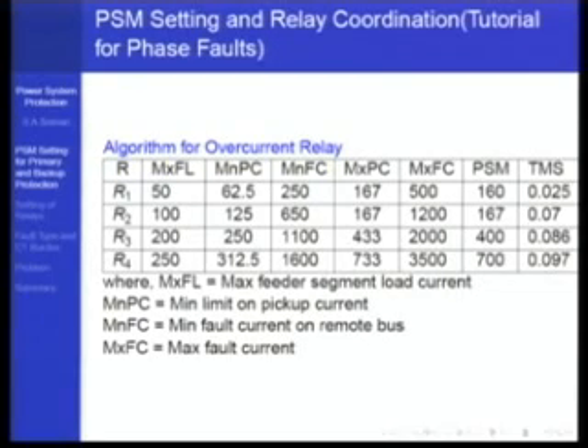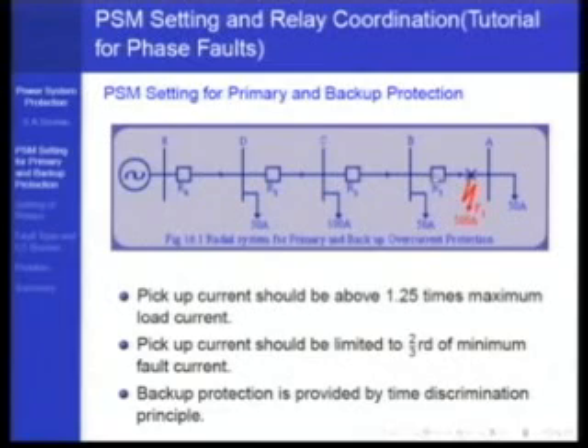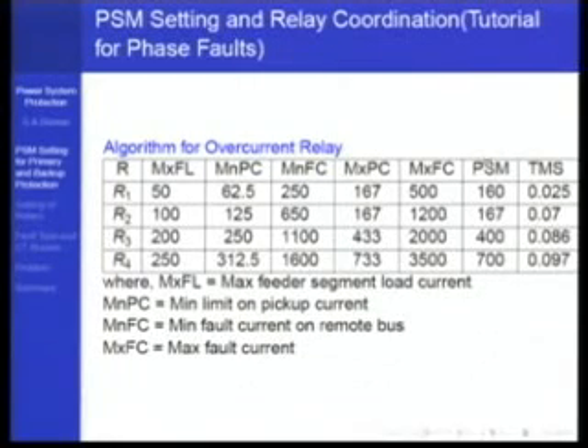The pickup current is 160 amperes. It's not the PSM, the pickup current is 160 amperes. And make the time multiplier setting as low as possible for this particular relay. R1 has no coordination responsibility, so its time multiplier setting should be as low as possible.